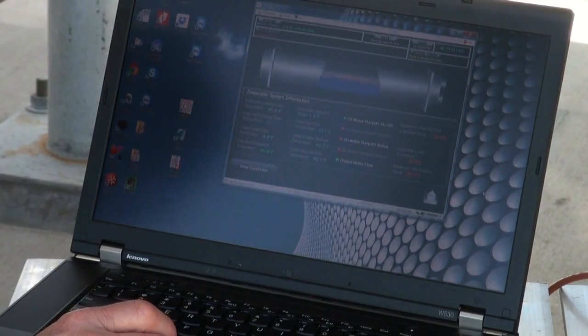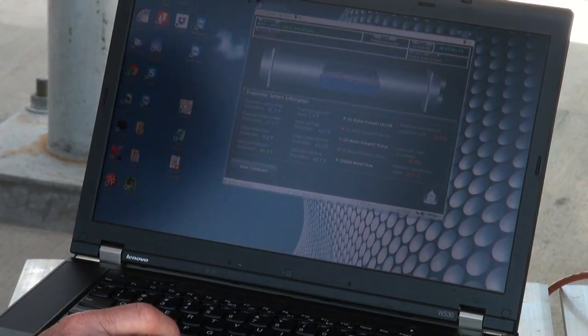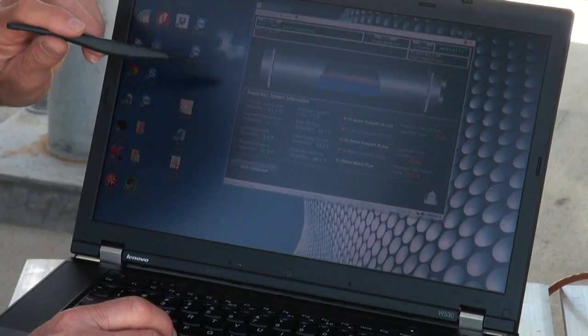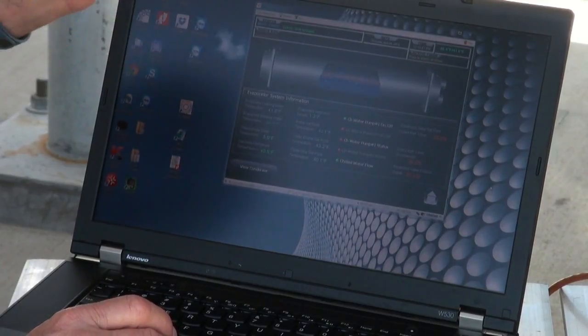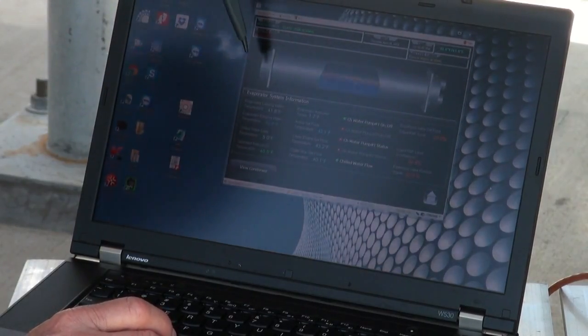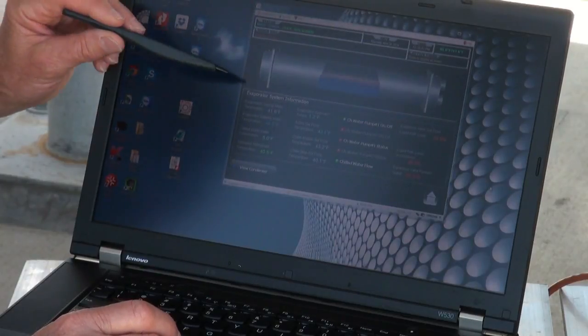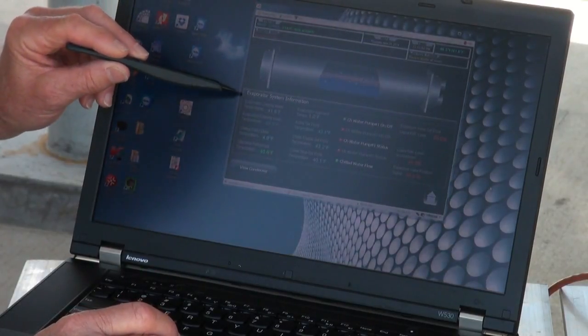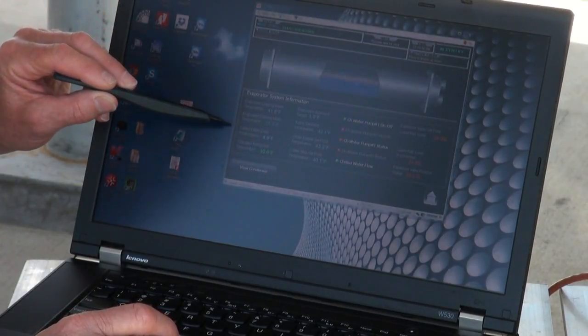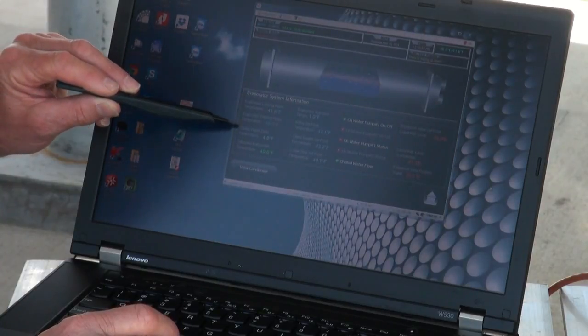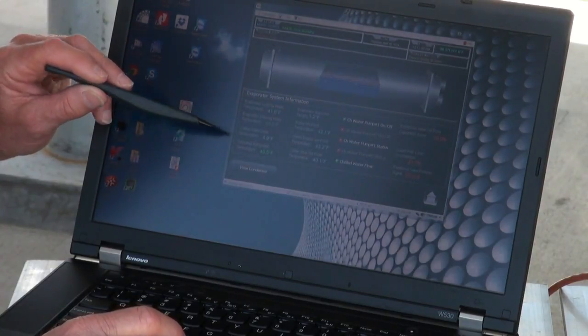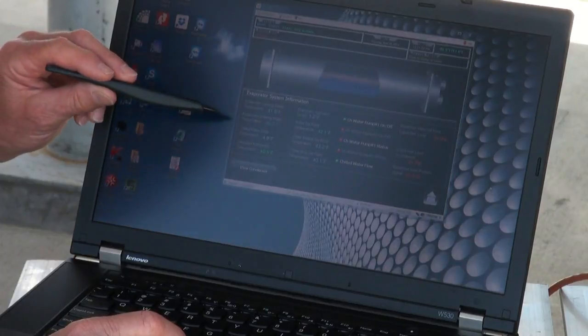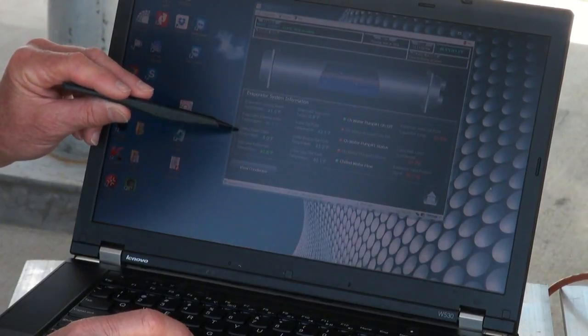This is the evaporator view. This is our chiller barrel. Again, we have our status window up here. We always have that on each page. You've got evaporating temperature, water temperature in and out. You've got the delta T, which is the difference in temperature from entering to leaving water. Right now we're running 4.9, 5 degrees.